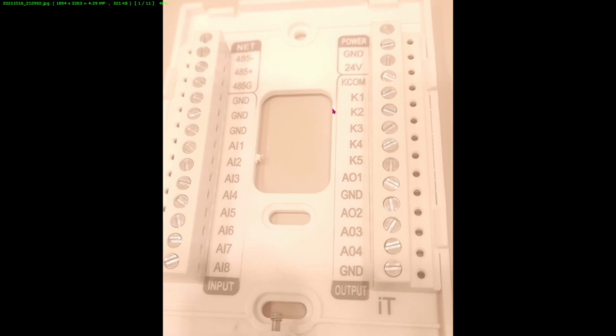And basically you provide a 24 volt power supply, you jumper that down to the K-COM, that provides 24 volts to all of the K terminals, which are basically relays, and they'll open and close. That is for opening and closing the zone valves or actuators. And then these are all of, for instance, in a typical situation, all of the temperature sensors from remote rooms.